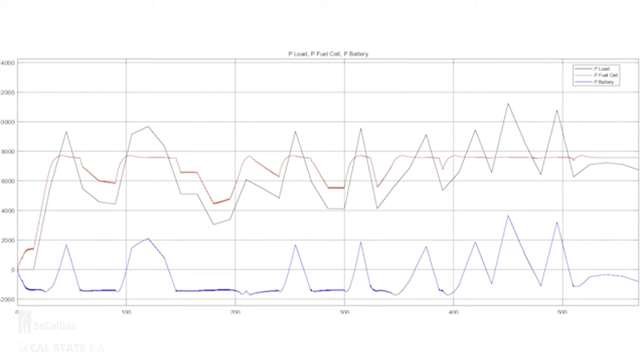Whenever the station load exceeds the fuel cell's maximum power, the battery begins to discharge. When the station's power demand is below the fuel cell's maximum, excess energy is diverted toward recharging the battery, which is why the blue line goes below zero watts at several points—drawing energy from the fuel cell rather than providing energy to the station. To avoid overcharging the battery, there is a current limit through the buck converter. The combined power demand from the station and recharging battery can sum to less than the fuel cell's maximum, so the fuel cell's output is reduced to compensate.